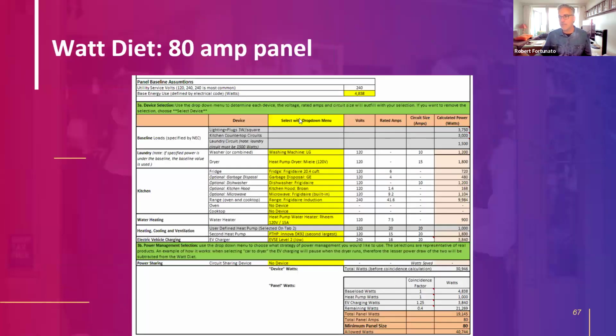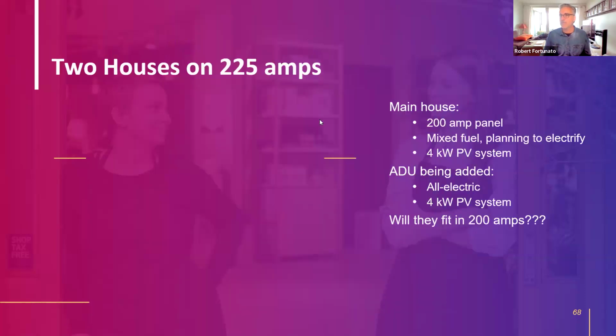We went through the calculations, and he was able to use his 80 amp panel to do everything he needed, including a heat pump. We did a 120 volt heat pump hot water heater, just plugged in, no special breaker needed. Point by point, these things are all possible, and it never exceeded the peak load. He never broke his main panel as a result, because of the coincidence factor we discussed earlier.